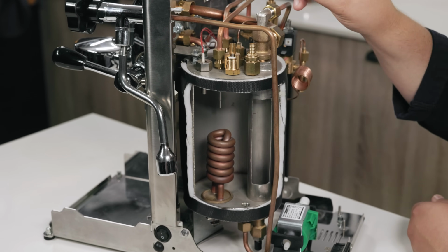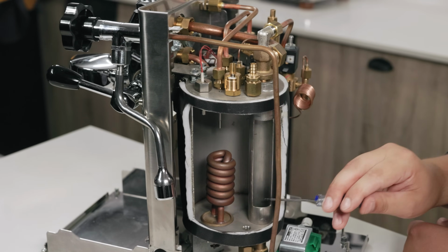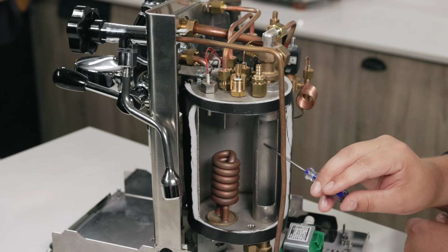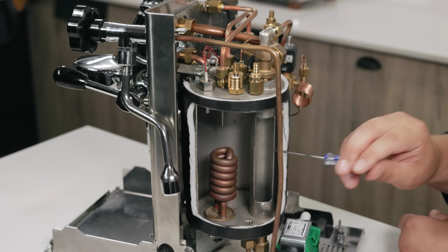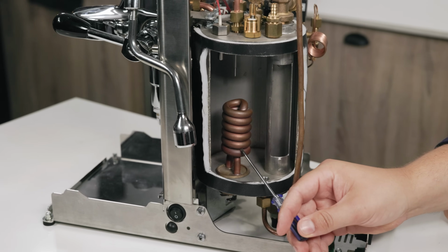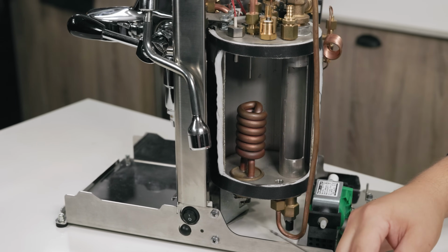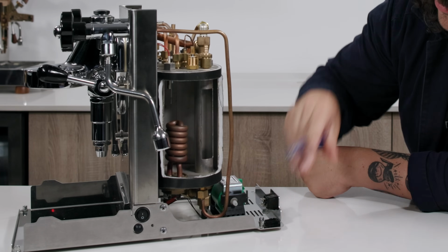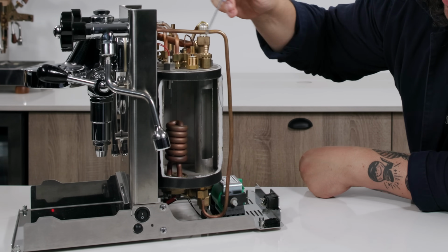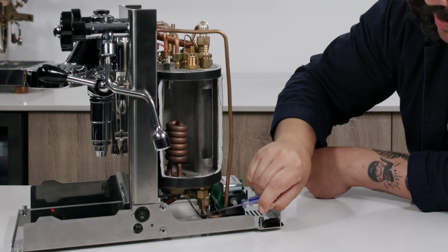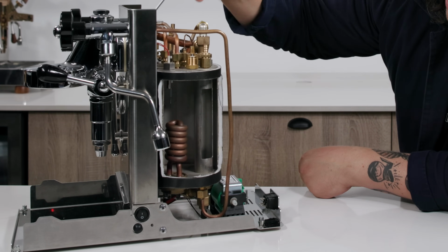Now, again, the thermosiphoning is very slow, so it's not like a ton of water's coming out of this at all times. A lot of it's coming from the cool inlet. Here we have the heating element for the boiler itself. So this is putting all the duty in there. If you're wanting to use the hot water, this is the simple route it takes. So it comes out from the bottom of the boiler, up and out as hot water.